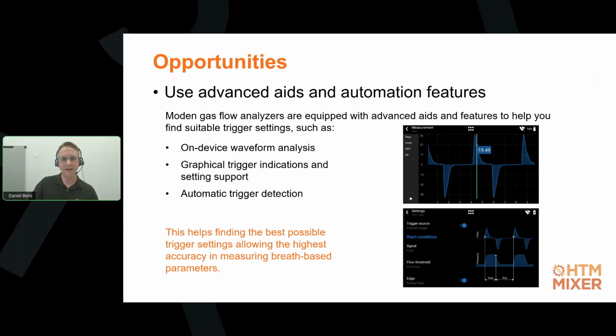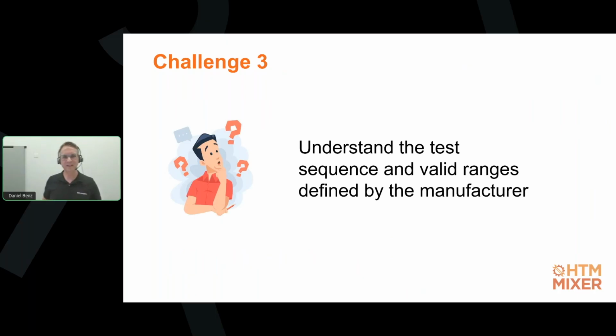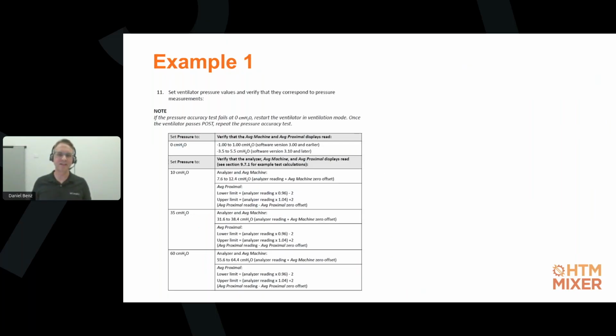All right, I'm going to shift gears a little bit and talk about the last challenge I wanted to discuss with you, and this is understanding the sequences and valid ranges defined by the manufacturers. Here is an example. I don't expect you to be able to read all that, but this is an extract from a service manual where it asks you to calibrate different pressure scale points. Basically, we need to set a certain pressure on the ventilator and then check if the pressure measured by the analyzer and the ventilator are within an acceptable range.